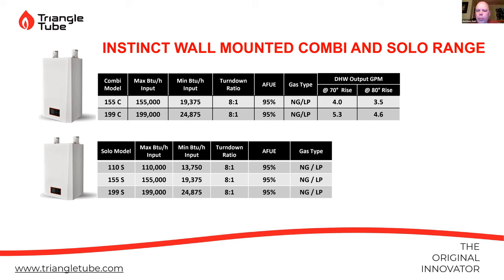Hey, Josh, we had a question pop through as to how far down you can derate the boilers. So we can technically go all the way down to zero, but I think there's a default. I think we get on the 155 down to about 60,000 BTUs, and the 199 is about 80,000 BTUs. If you have questions, reach out to us directly. I have some charts that give you some percentage to the output, and also a calculation on that as well. So if you do want more info, contact me on that, or you could email tech services and we can send that directly.